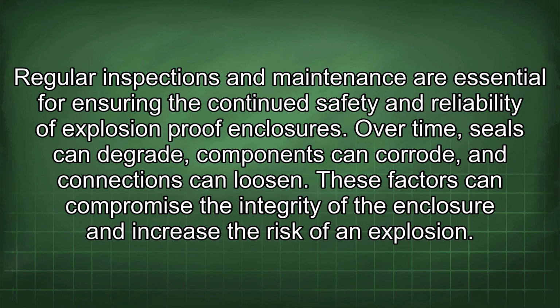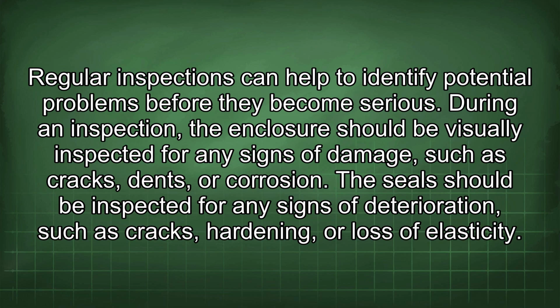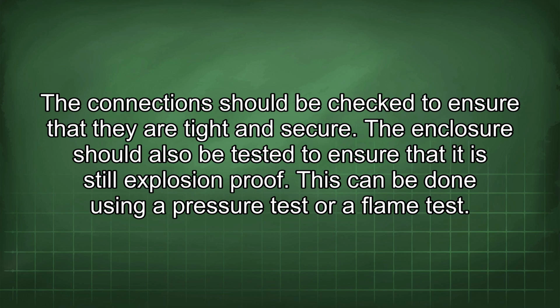Regular inspections and maintenance are essential for ensuring the continued safety and reliability of explosion-proof enclosures. Over time, seals can degrade, components can corrode, and connections can loosen. These factors can compromise the integrity of the enclosure and increase the risk of an explosion. Regular inspections can help to identify potential problems before they become serious. During an inspection, the enclosure should be visually inspected for any signs of damage such as cracks, dents, or corrosion. The seal should be inspected for any signs of deterioration such as cracks, hardening, or loss of elasticity. The connections should be checked to ensure that they are tight and secure.